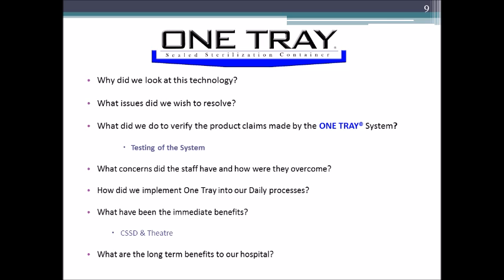turning into vapor and venting off through the filter. But we wanted to make sure that the OR and the staff upstairs understood that this in no way meant that it was contaminated, that it was essentially sterile water in nature, if they happened to send something up rapidly and needed it immediately turned over. Our biggest concern was making sure that when we had these quick turnovers, they allowed the instruments to cool, or had a system in place to cool the instruments, so that larger, heavier metal instruments weren't a danger to the patient, because that's how fast we were able to turn these instruments over. So they still had to make sure that they didn't put a hot instrument on the patient.